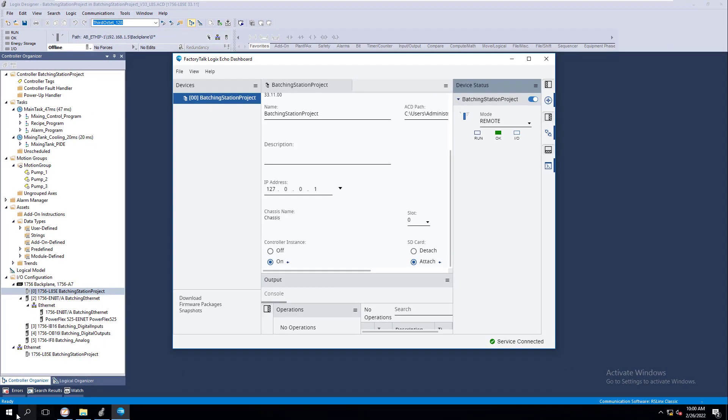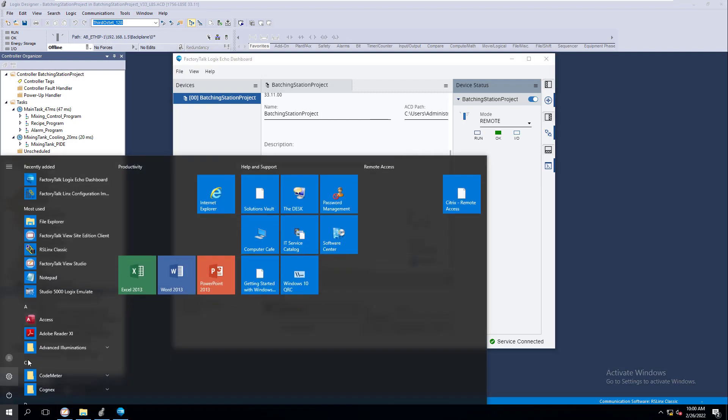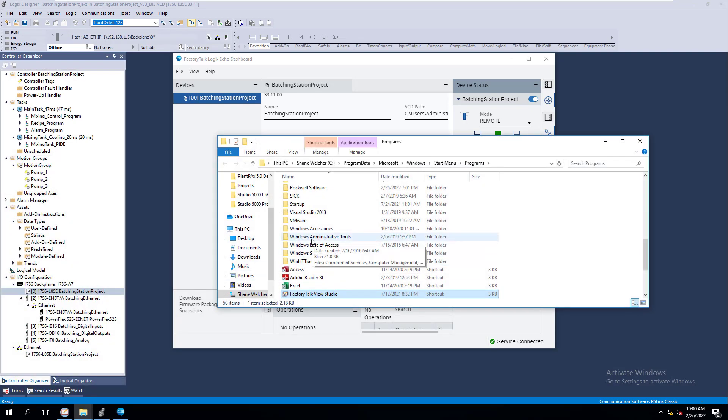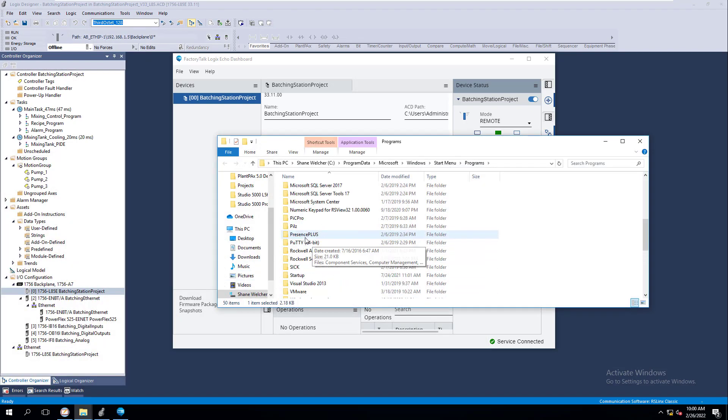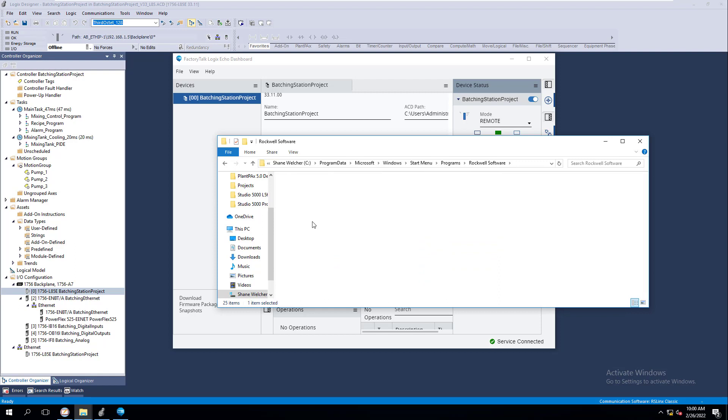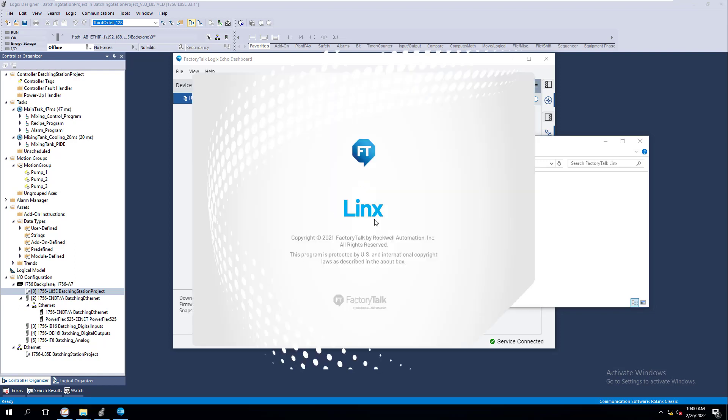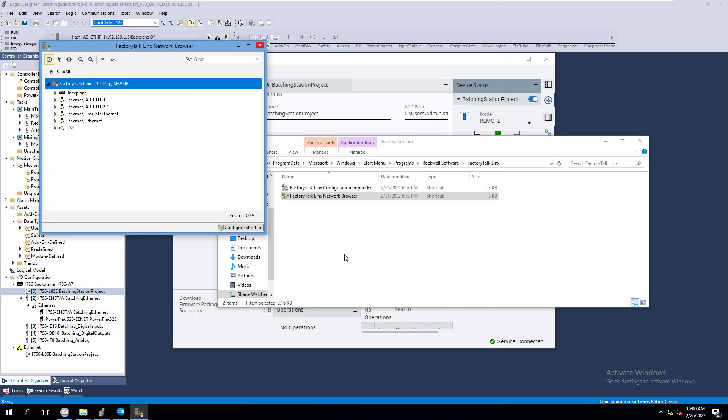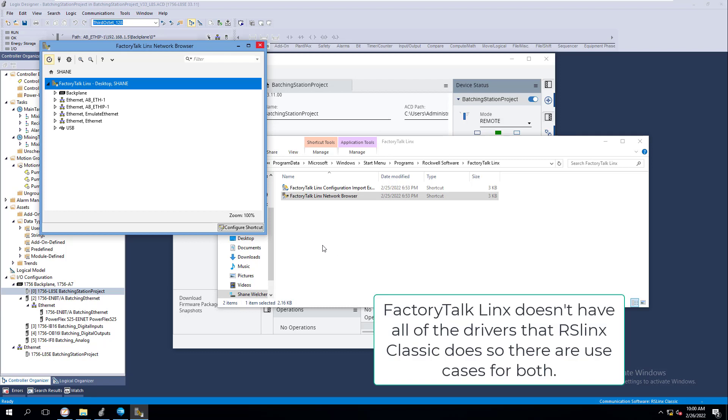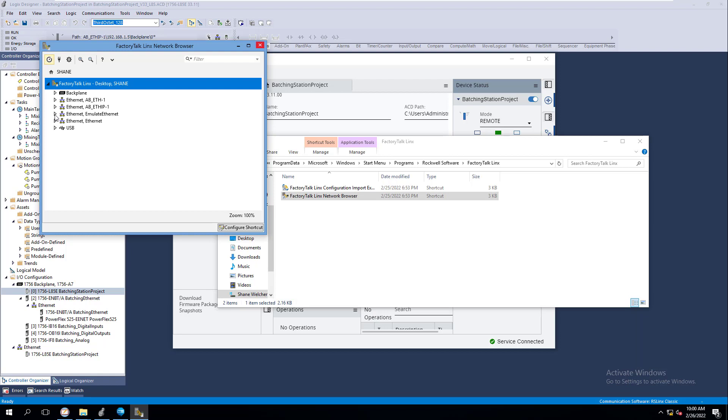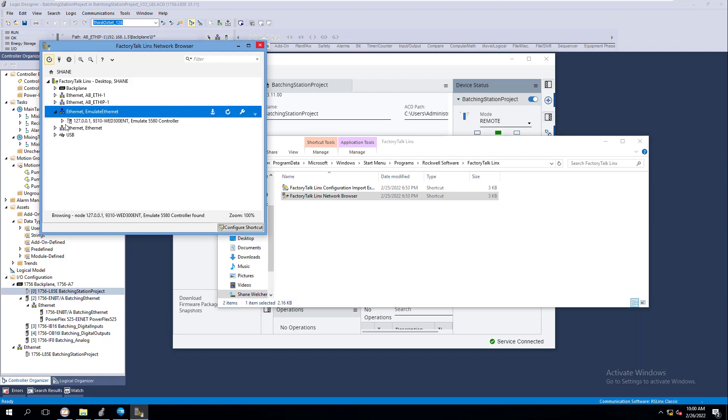So if we're coming in here and we're looking for the FactoryTalk Linx. So here's the software. So we're going to go to FactoryTalk. We're not going to go to RSLinx. We're going to go to FactoryTalk Linx. So FactoryTalk Linx now, if I open up FactoryTalk Linx, very, very similar and can be used basically as a substitute for RSLinx, but it does have a little bit of drawbacks. It doesn't have the older drivers and stuff like that if you're currently using older drivers. But if you're using this Logix Echo, this is what you use. You can see right here, I'm currently live. This is my project that I have in here.